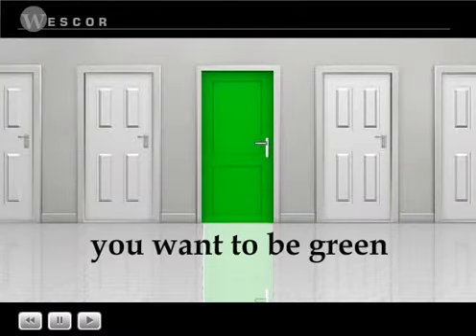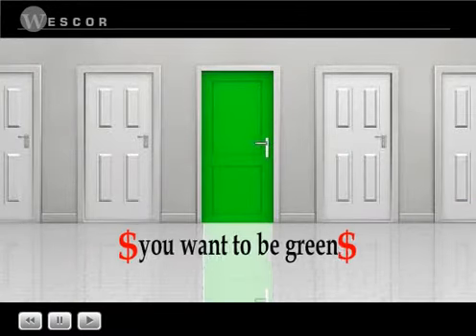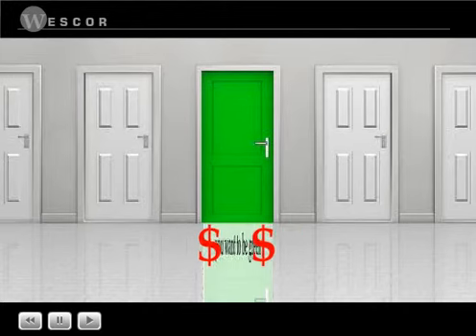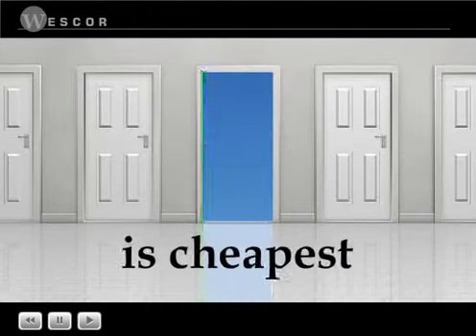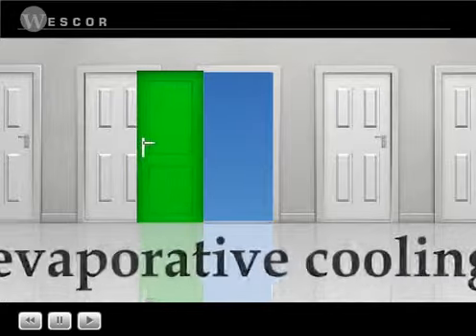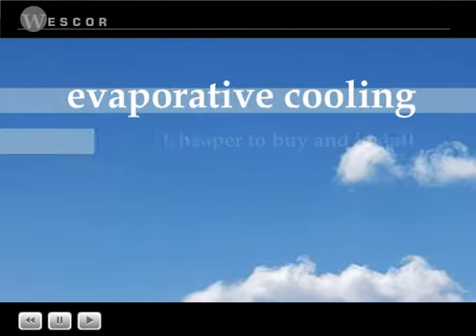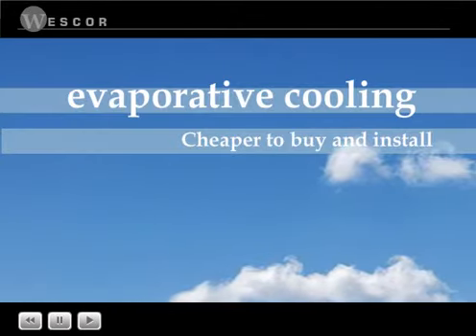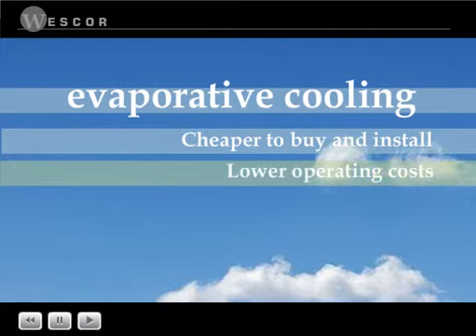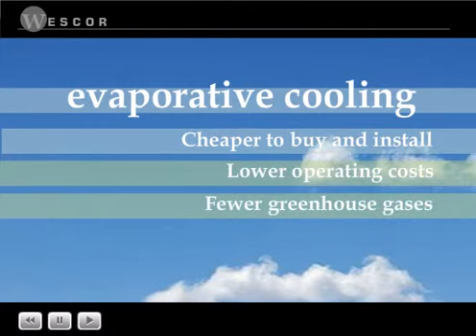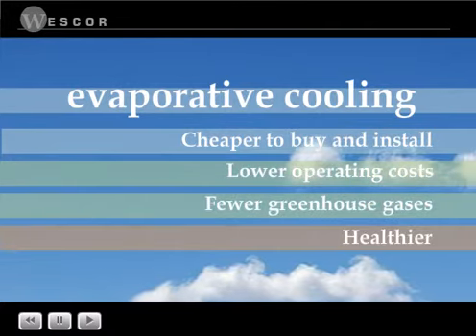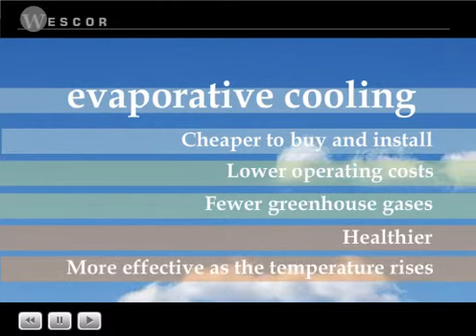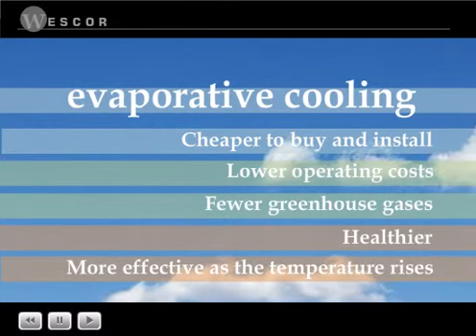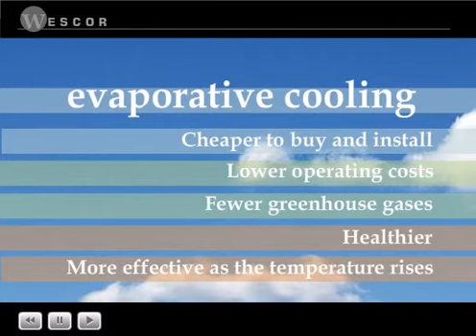Sometimes, as much as we want to be green, economic constraints force us to settle for a less environmentally friendly solution. But for cooling, the greenest solution is the cheapest solution: evaporative cooling. Evaporative cooling is cheaper to buy and install than traditional air conditioning, has lower operating costs, produces fewer greenhouse gases, and is healthier. Plus, unlike traditional DX air conditioning, which becomes less effective as the temperature rises, evaporative cooling becomes more effective as the temperature rises.